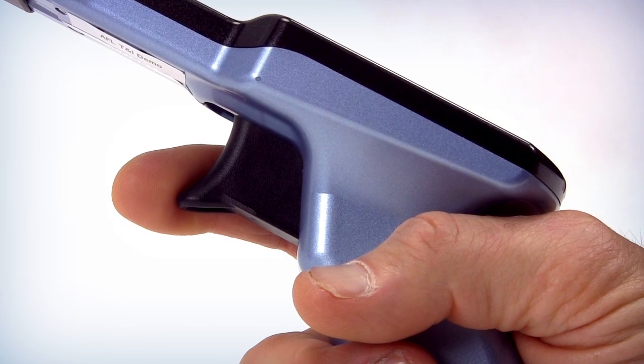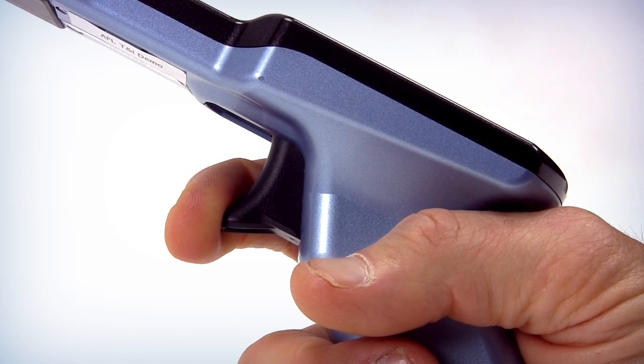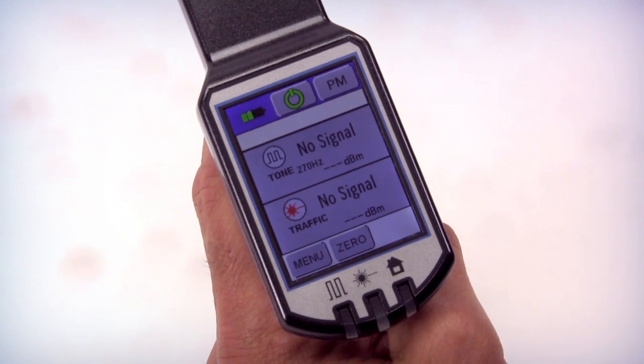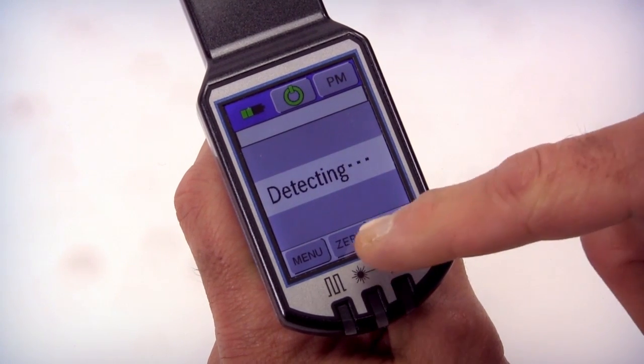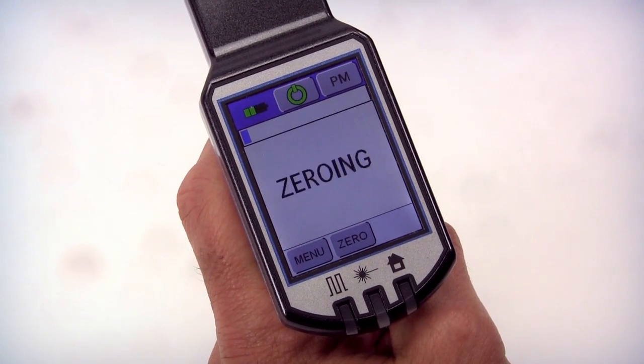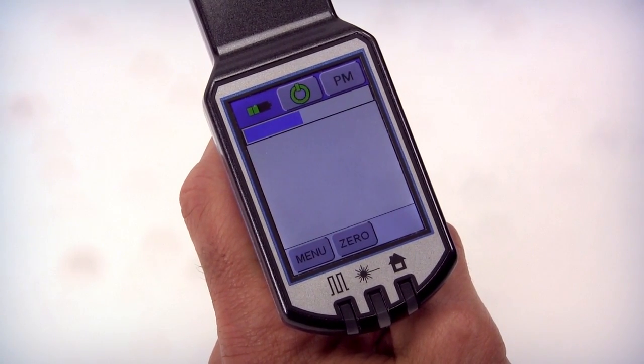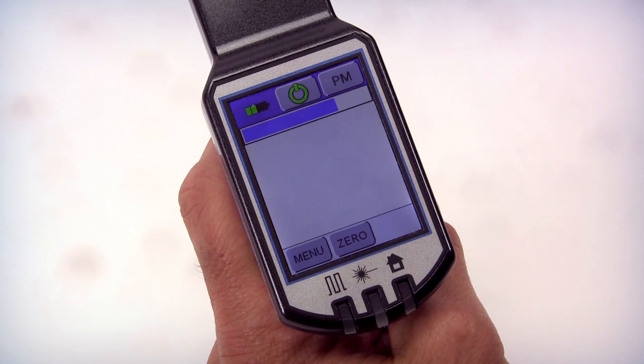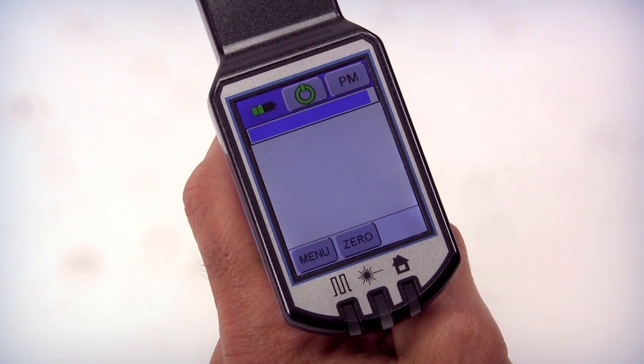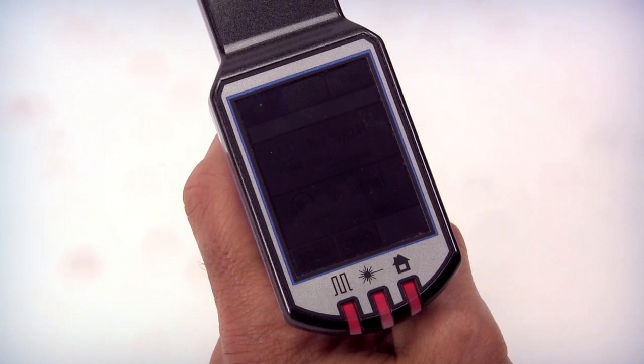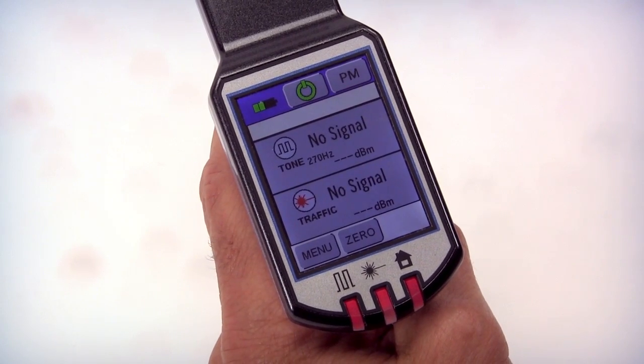This is accomplished by pulling the trigger and holding it. If the trigger lock is engaged, simply pull the trigger and release it. Now select the zero button located in the lower center of the touch screen. The screen should flash zeroing for approximately three seconds before returning to the measurement screen. The device is now ready to take measurement.